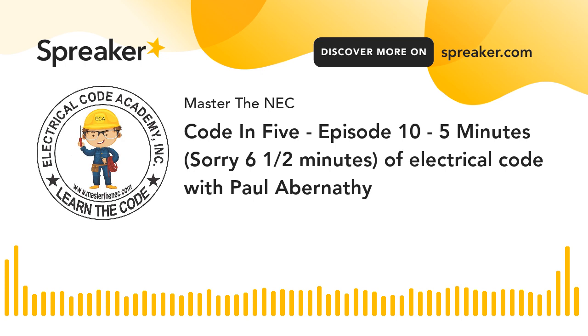So let's talk about (a), the terminal provisions, 110.14(C)(1)(a). If the equipment has terminals and it's rated 100 amperes or less, or the conductors that are terminating are size 14 through 1 gauge, then they shall apply to either 1, 2, 3, or 4 under 110.14(C)(1)(a). So if we don't know what the device terminals are rated, or what the overcurrent device terminals are rated, which could happen, then we know that if the conductors are between 14 and 1, or if it's 100 amperes or less, our ampacity value is going to be very much in line with the 60 degree, and we're going to use at least 60-degree rated insulated conductors.